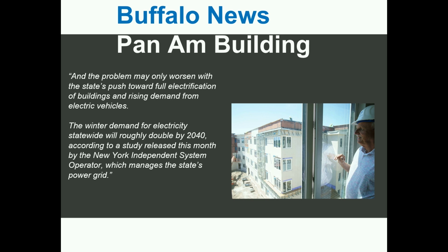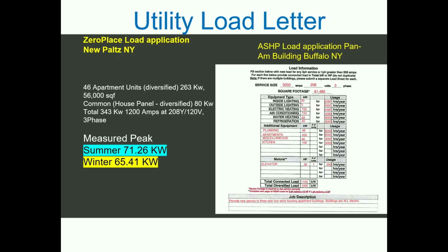What the article didn't show, first of all, here is the load letter for that development, and this is for each one of those 50 apartment buildings. So they're about the same size each as actually Zero Place. You might not be able to see this. This is 61,000 square foot. Zero Place was 56,000 square foot. Actually a worse climate zone than Buffalo, New York, which we, coming from Buffalo, can hardly understand and believe.